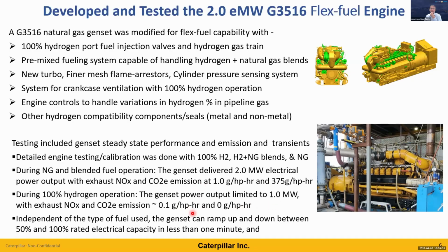One advantage of running 100% hydrogen is that the NOx emission went down to about a 10th or less than a 10th. It was about 0.1 gram per horsepower hour compared to 1 gram with natural gas. And there was no CO2 because hydrogen fuel doesn't have any carbon. There is a trace amount that comes from the lube oil burning, but other than that, there is no CO2 going in with the fuel.